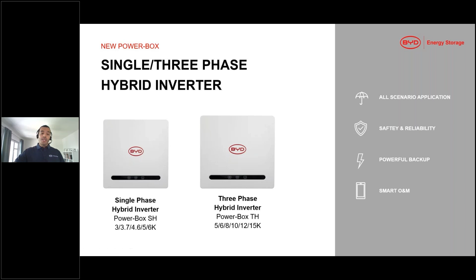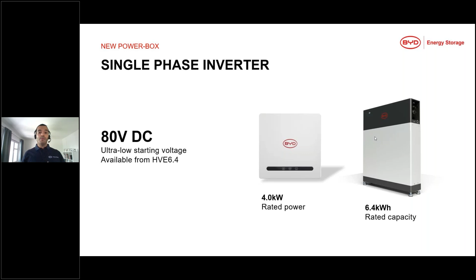Some advantages about those inverters: especially the single phase inverter, which comes in compact power classes, has a very low battery voltage parameter requirement. It can start with just 80 volt DC of the battery, so it's possible to start with just one module, namely the 6.4 kilowatt hour bigger module. Then you have a very compact system with one single phase inverter and that one module of 6.4 kilowatt hours. You can have up to 3 of those inverters connected in parallel, every one of those inverters with a battery connected to it.